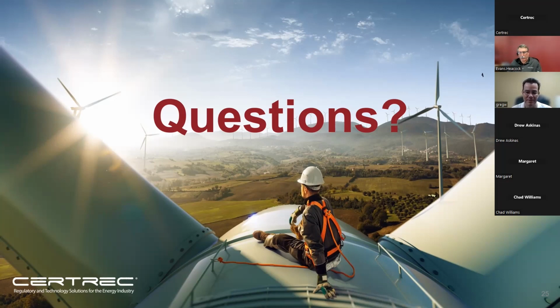So from a standpoint of the overall reliability of your device, how reliable do you say your device is, given the history that you've had so far? Well, it's interesting because our design team is really largely from the portable instrument world, test and measurement. In portable equipment, that equipment has to provide the electrical signal and record it, because those tests are typically performed in an offline environment, either periodic test or diagnostic. So things are offline and isolated, and the test equipment has to put out the signal and record the response.